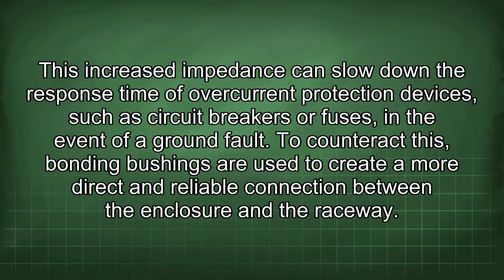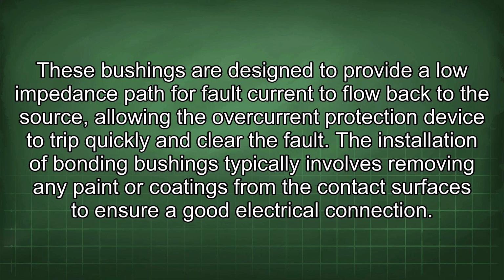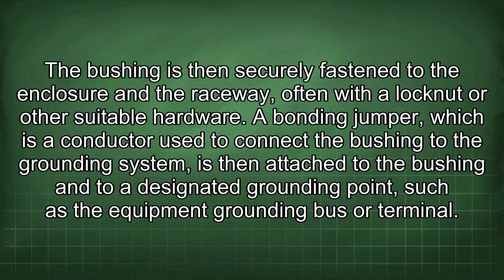To counteract this, bonding bushings are used to create a more direct and reliable connection between the enclosure and the raceway. These bushings are designed to provide a low impedance path for fault current to flow back to the source, allowing the overcurrent protection device to trip quickly and clear the fault. The installation of bonding bushings typically involves removing any paint or coatings from the contact surfaces to ensure a good electrical connection. The bushing is then securely fastened to the enclosure and the raceway, often with a locknut or other suitable hardware. A bonding jumper, which is a conductor used to connect the bushing to the grounding system, is then attached to the bushing and to a designated grounding point, such as the equipment grounding bus or terminal.